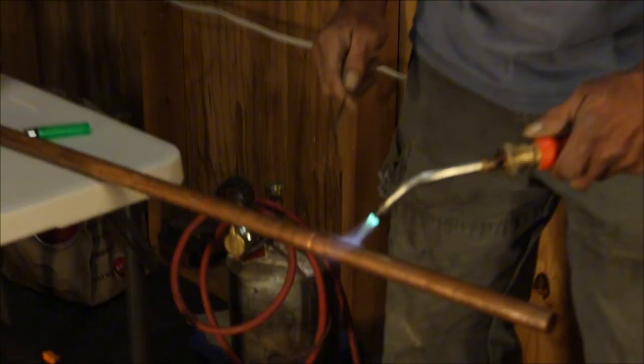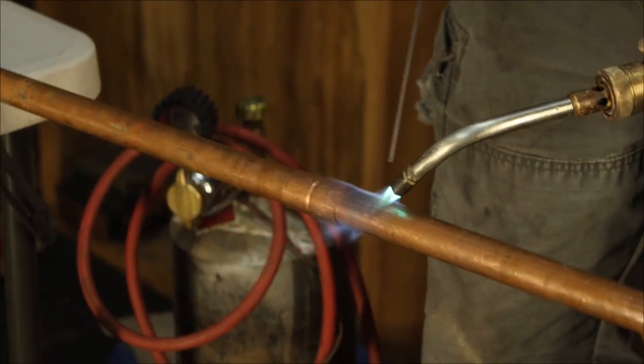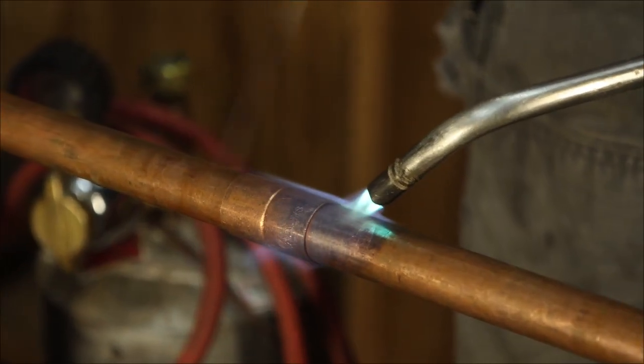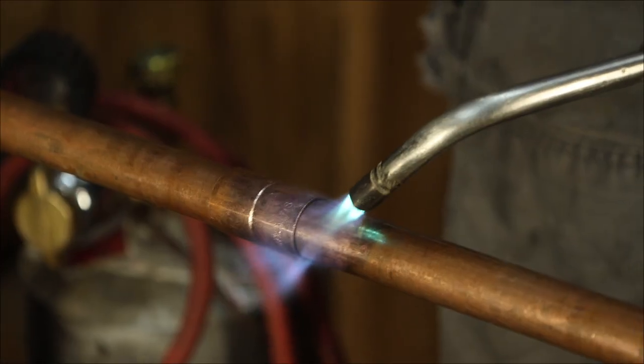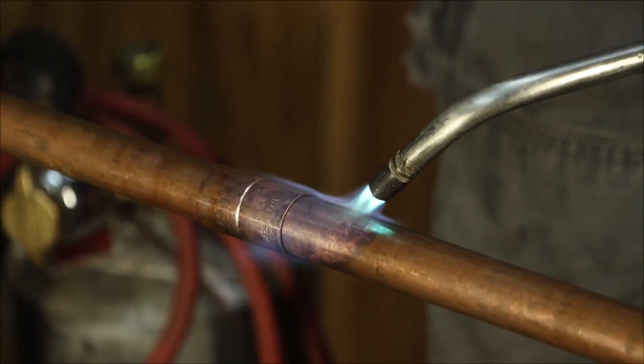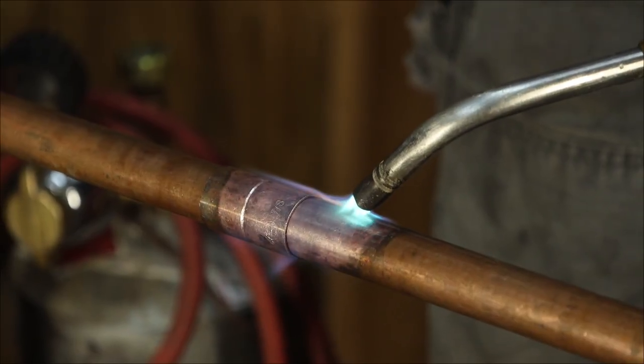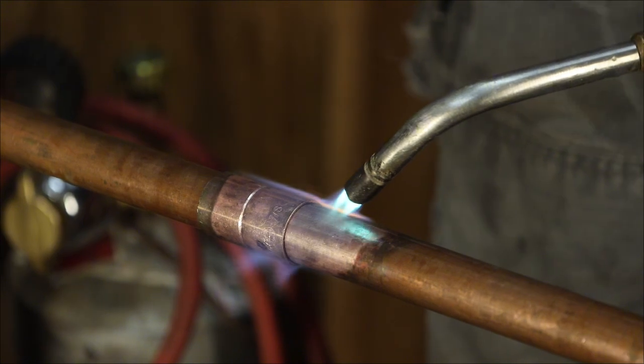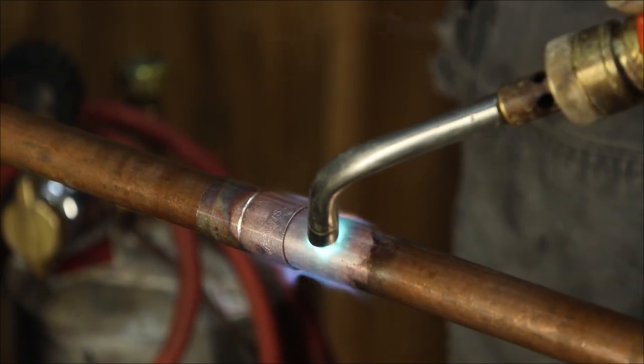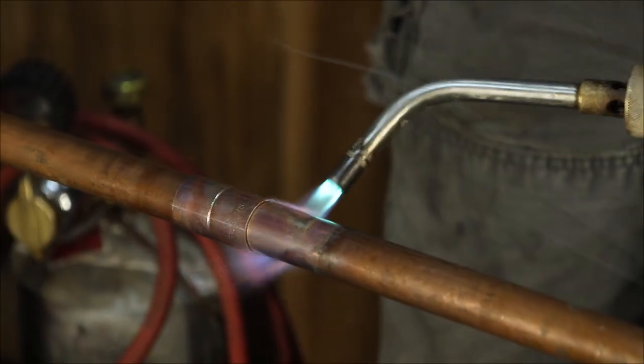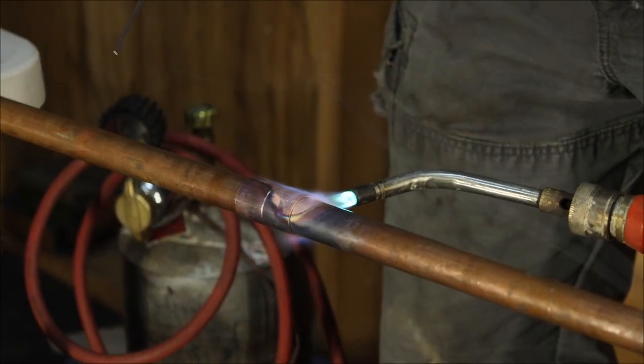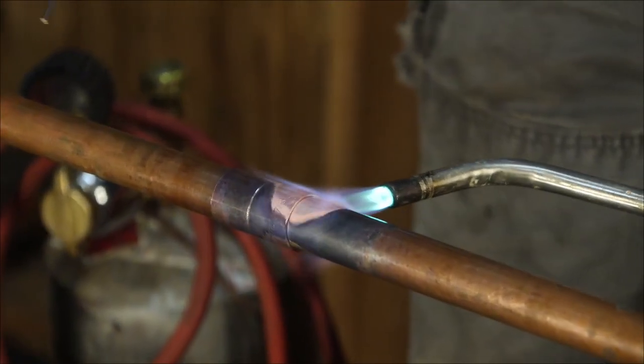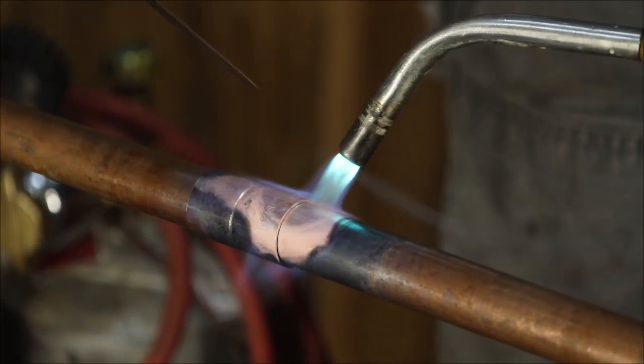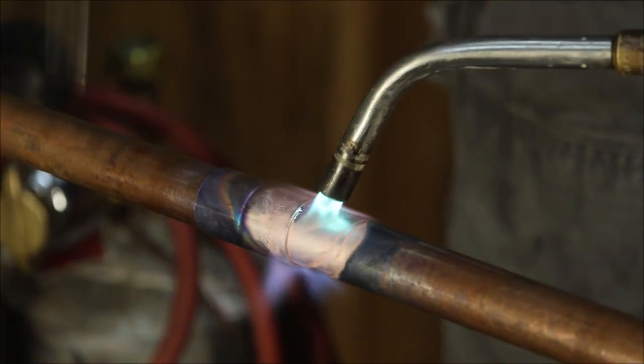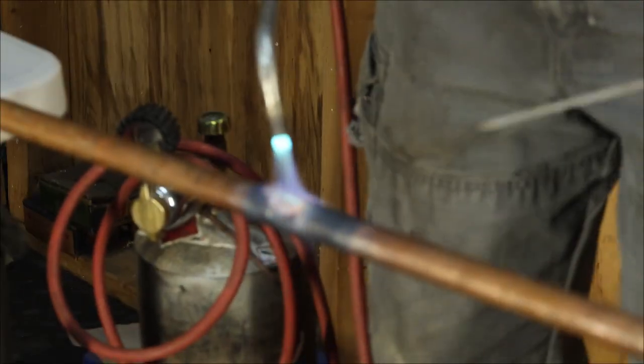All right, as I said, I'm heating the copper, but I have my flame running onto the coupling so that I'm actually heating both at the same time, with most of my heat on the copper that goes into the coupling. As it begins to get hot, I can move my torch around a little bit, because you can put all that heat in one spot and literally burn a hole in the copper. So you want to rotate it. Now you can see your brazing rod is ready to melt. Now I want to move the flame while I'm still keeping both pieces hot.